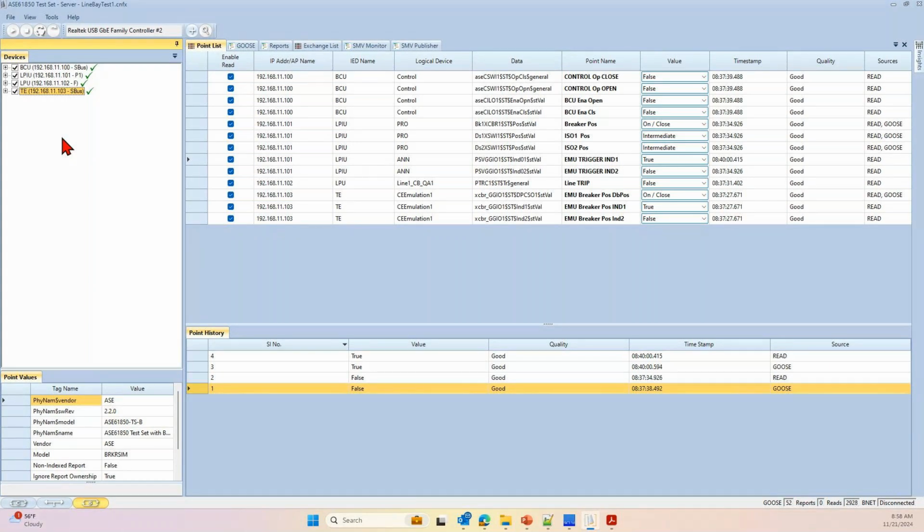The next question I have is how the BNET was used in the IOP. To talk about the BNET participation, we did not actively participate using the BNET. It was only acting like a sniffing tool to monitor the currents and voltages. What we did is we listened to the traffic and displayed the RMS values and also detected the delays in the network.